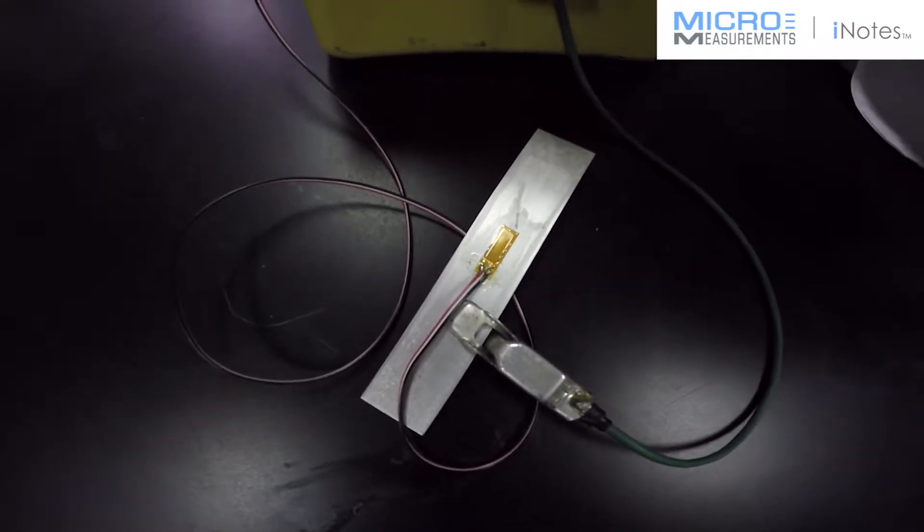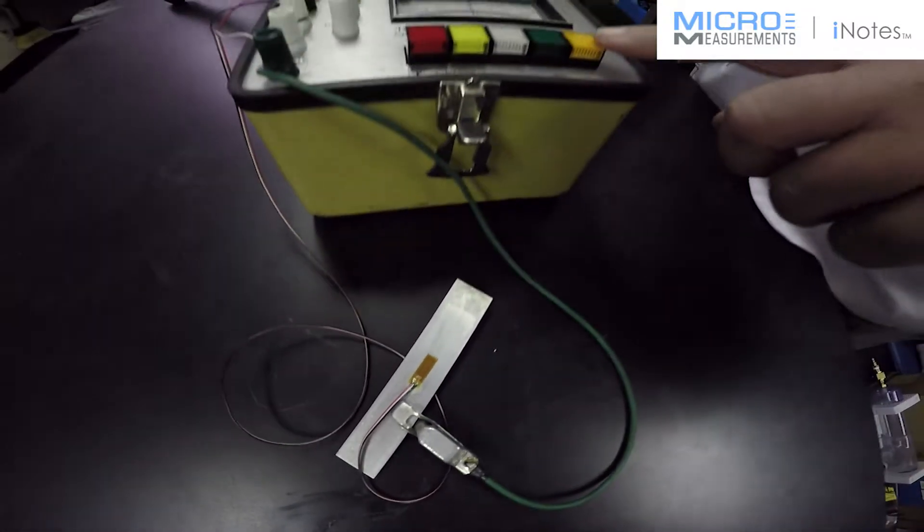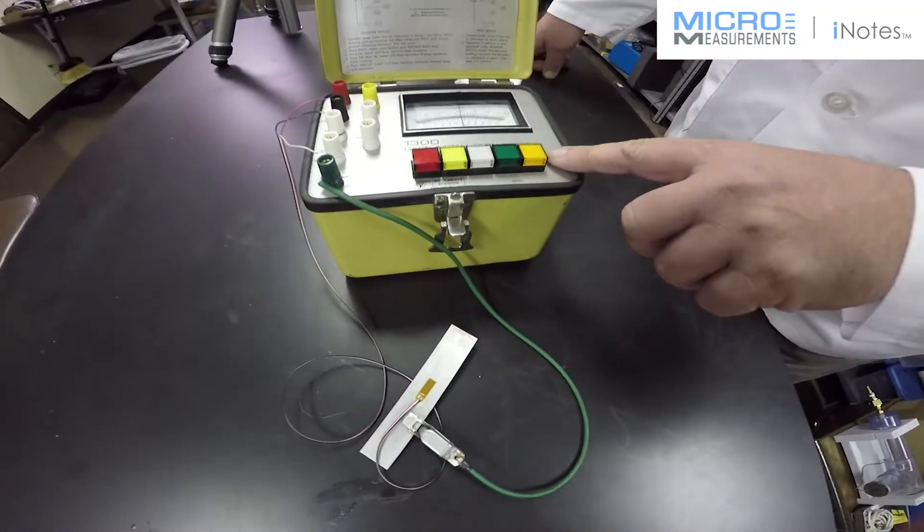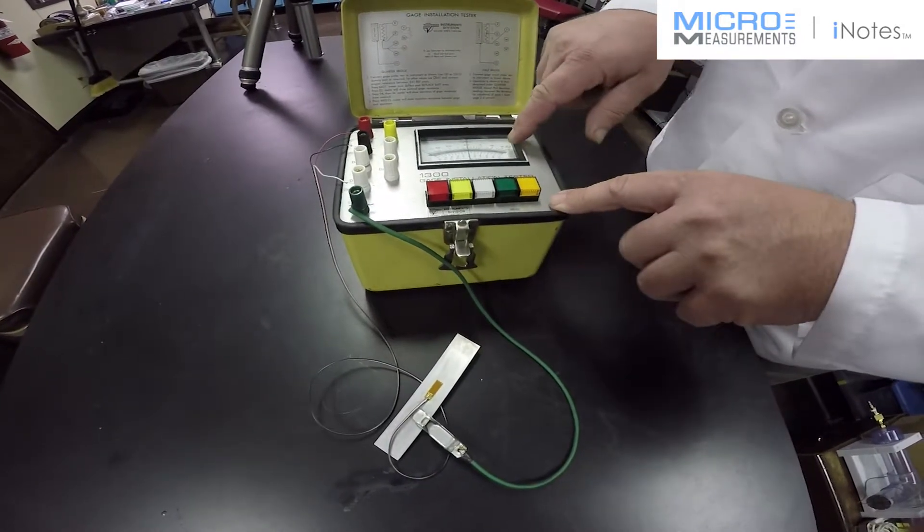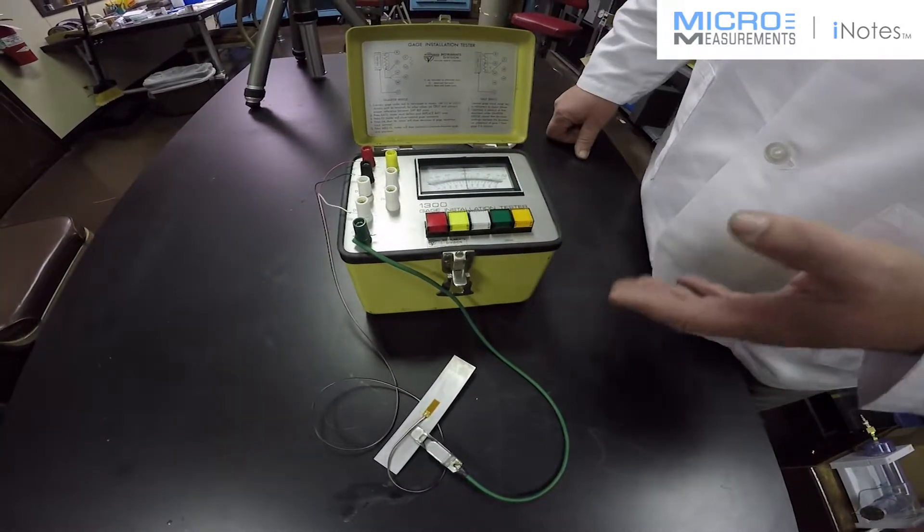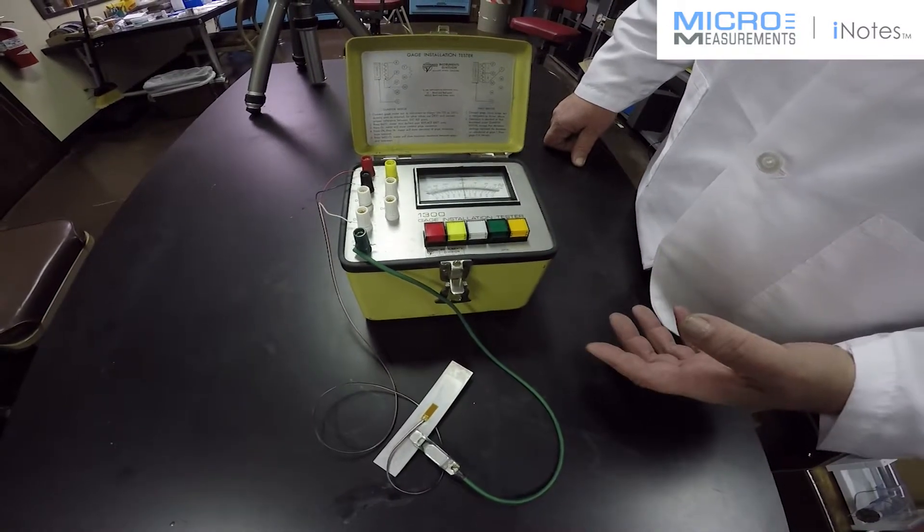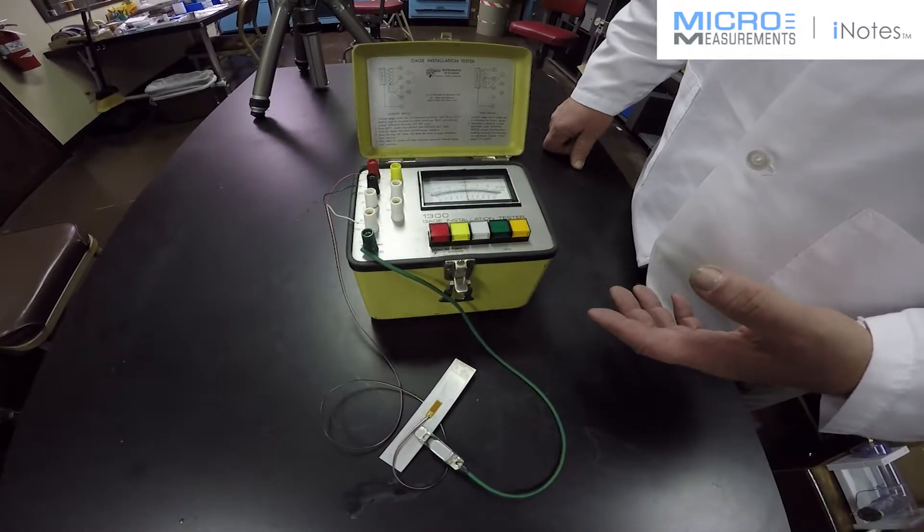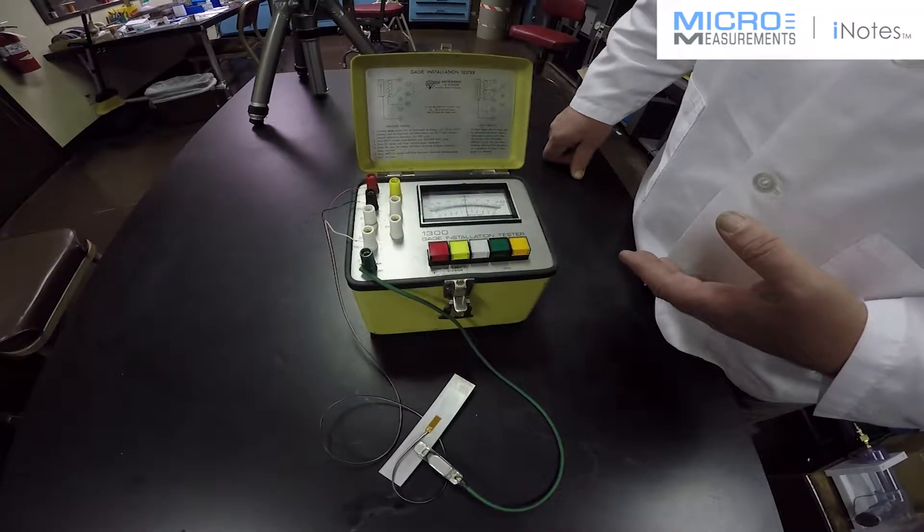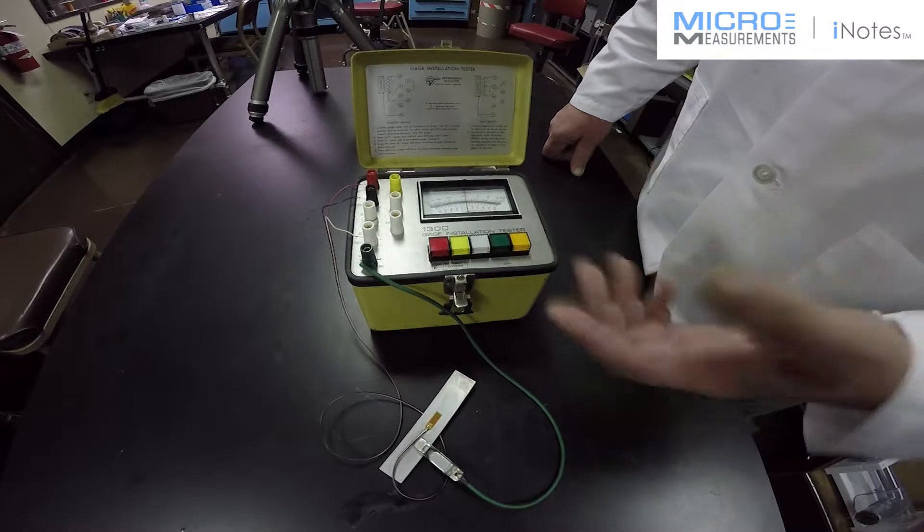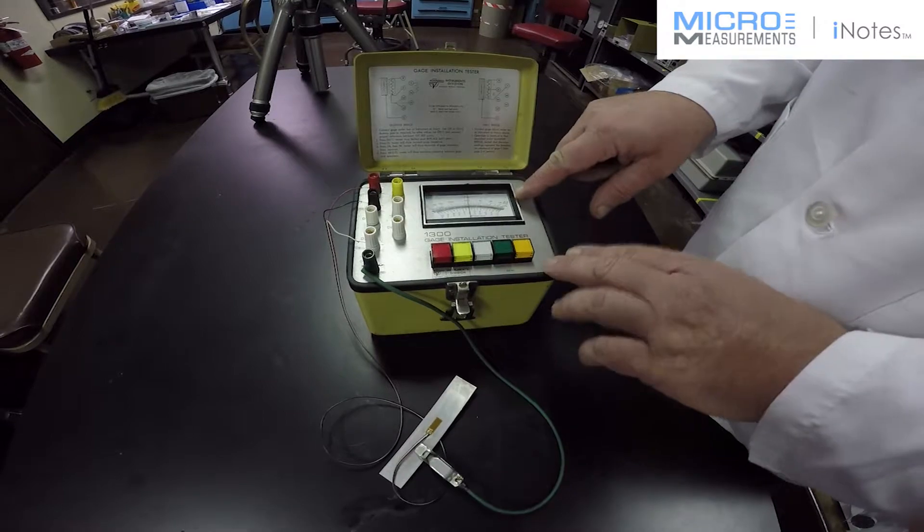So the Model 1300 accomplishes a mega ohm check using only two 9-volt batteries, about 15 volts. Now it's not a high accuracy test, but with a strain gauge, you're not interested in a high accuracy mega ohm resistance to ground reading. What you really want to know is, is it less than or greater than 10,000 mega ohms? So it's really kind of like a go or no go check. You don't need that high precision and the higher voltage that come along with that.